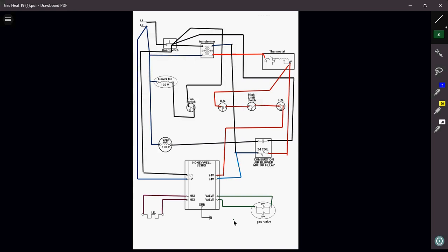It's also going to prove whether or not I have a clear flue pipe and an intact heat exchanger, simply due to the fact that I have a pressure switch in there to sense the pressure difference inside my heating unit. Once my pressure switch closes, it is now going to send that power down to my ignition module, telling the ignition module that we do have a call for heat. The ignition module will now send that signal out to our hot surface igniter, which will then begin to glow bright red.